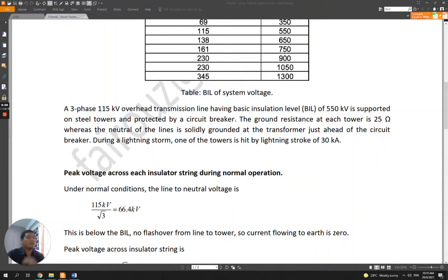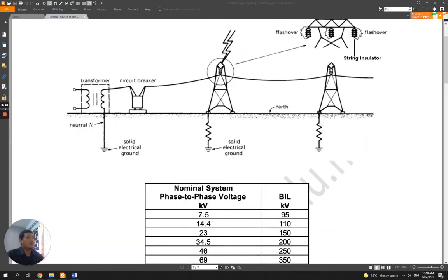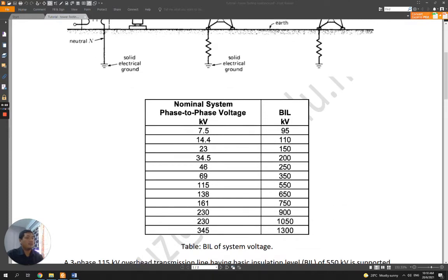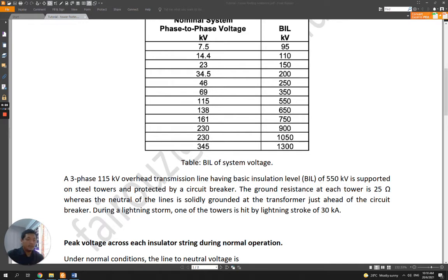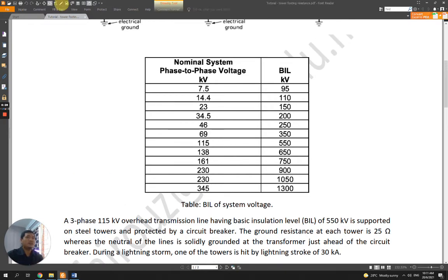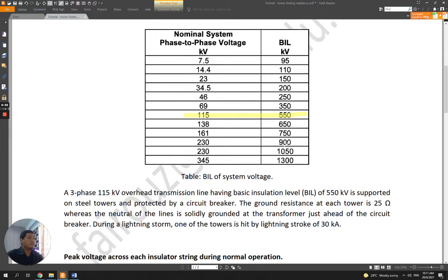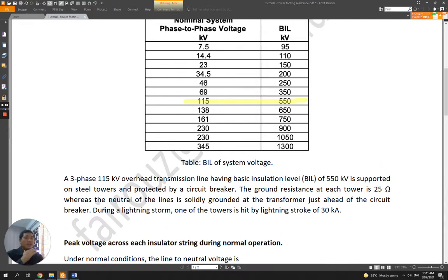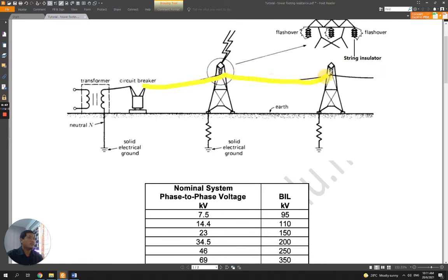In this video, we will look at an example when lightning strikes a tower. So we have a three-phase 115 kilovolt overhead transmission line, with a nominal system of 115 kilovolt, and it has a basic insulation level, BIL, of 550, as we can see in the table here. 550 kV for the BIL, and the line is supported on steel towers and protected by a circuit breaker. So this is the line, supported by a steel tower, and then the line is also connected to the circuit breaker.